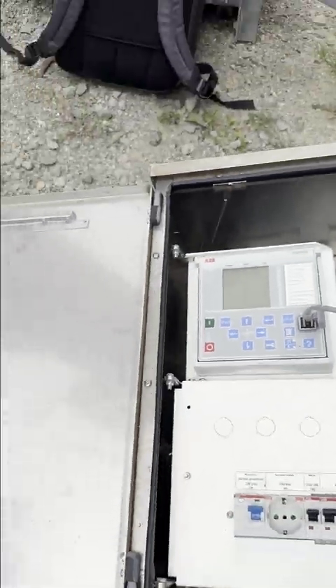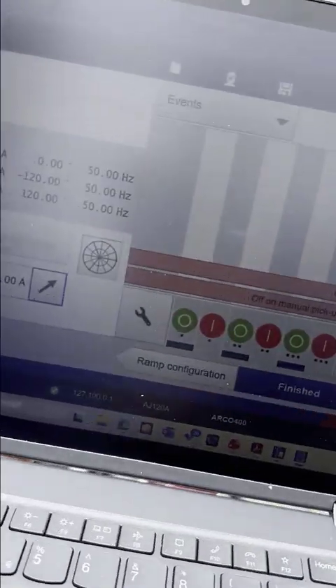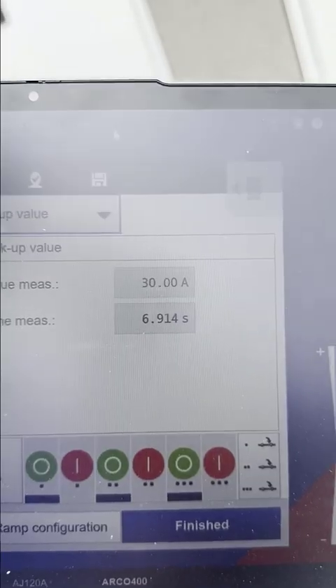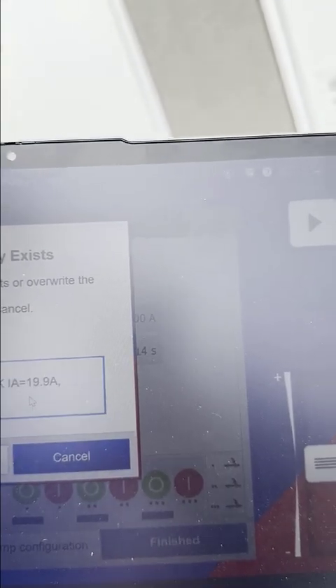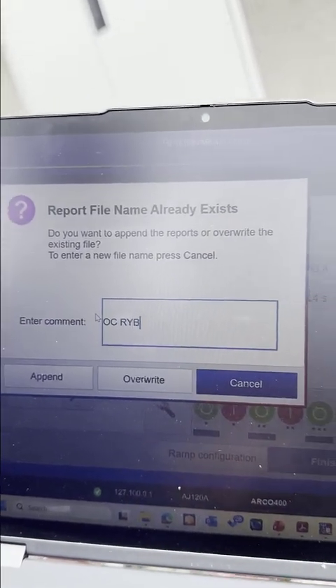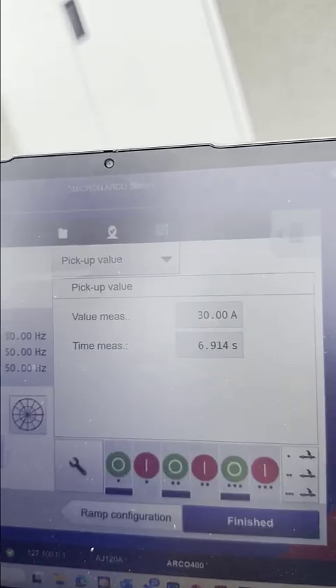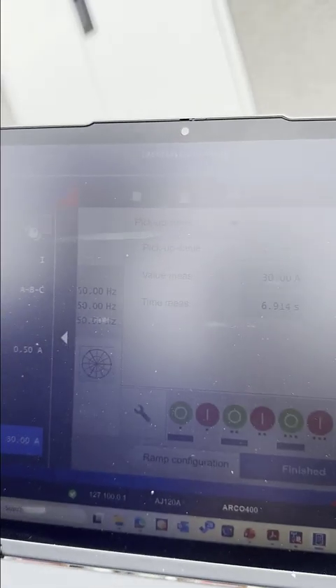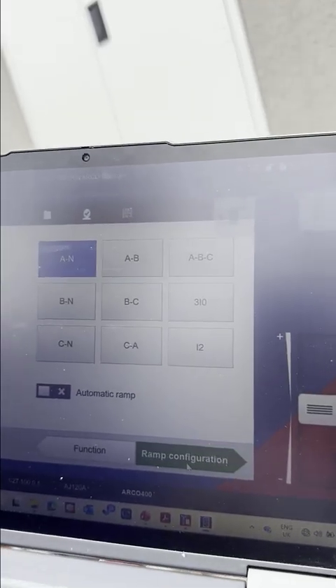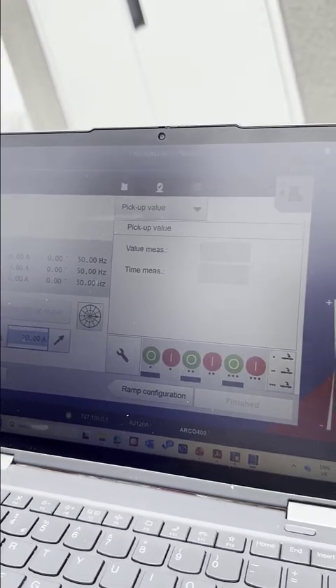You can select the manual pick-up signal. After you click this manual pick-up signal, you can see now the measured values of the pick-up value, which is 30 amp. Then you can save this value as well. You can give it a comment to be overcurrent RYB pick-up test. Then you can click append. Also, you can get back again from this navigation pane here, and you can select a different fault type to test the earth fault. Then you can go for the ramp configuration again, and you can start from 0, for example, because we are expecting 12.